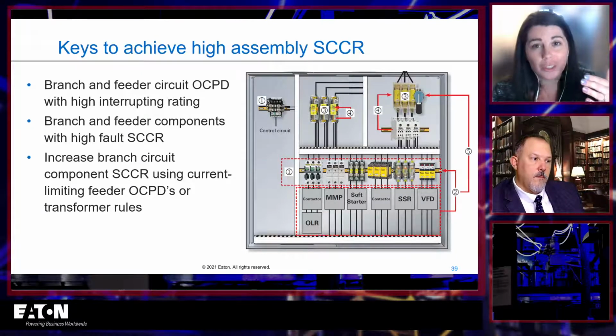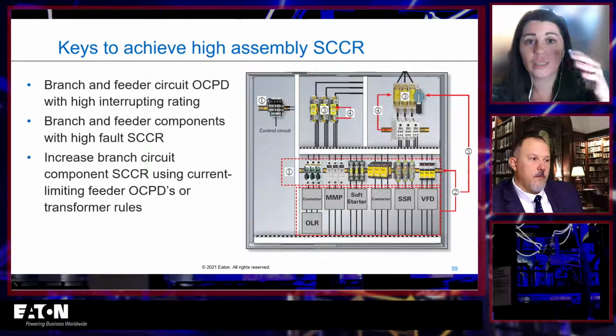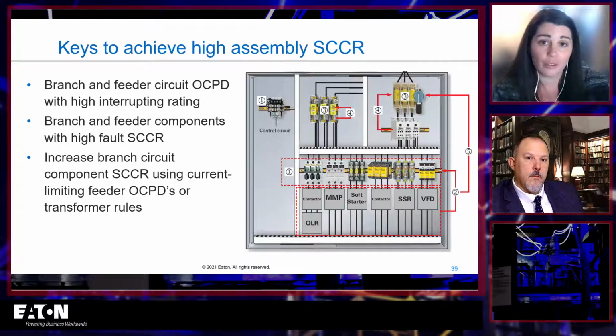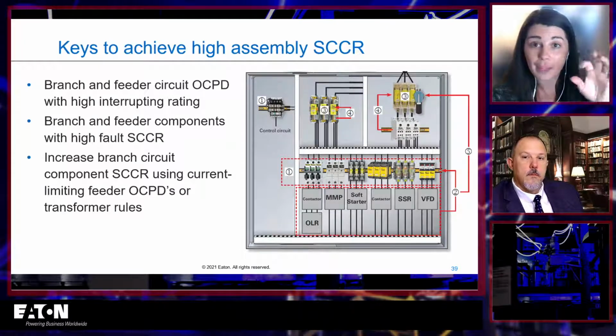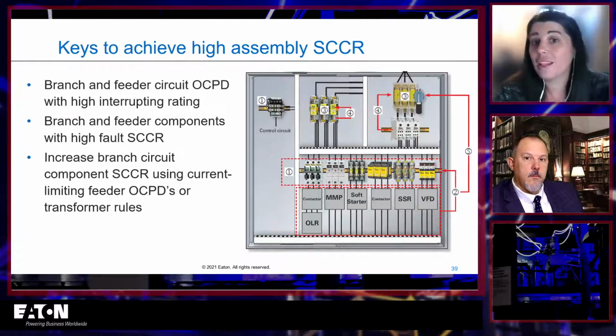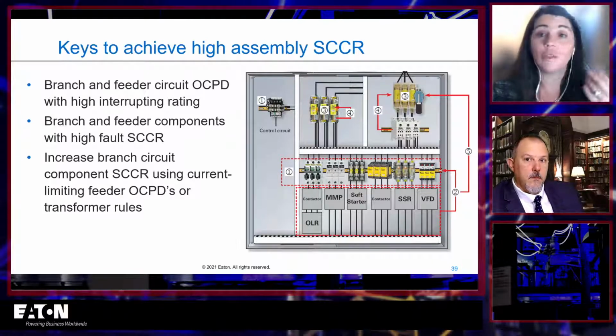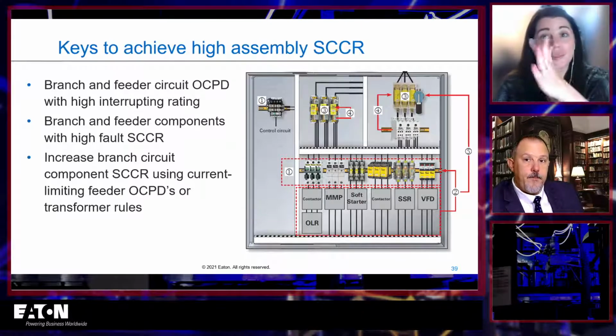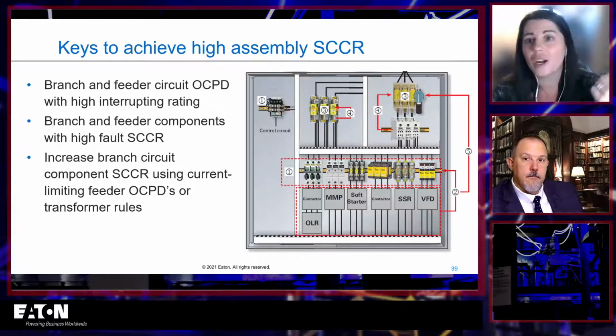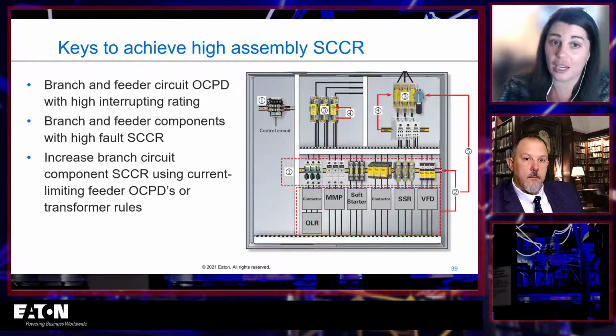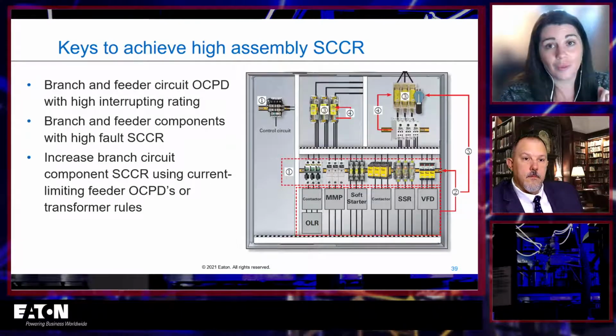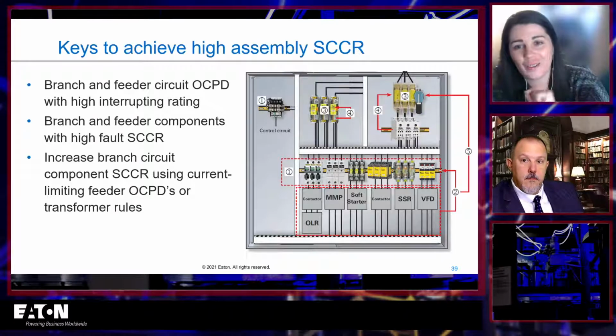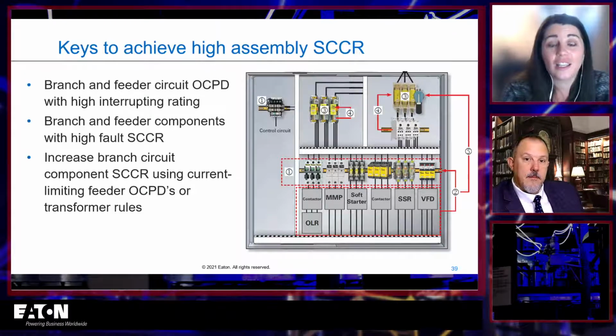Low short circuit current rating equipment usually comes from people who don't take advantage of that. They wind up with that standard, low fault rating because that component probably has a high fault rating if you use something specific in front of it, and they just didn't use that. They used something else which might cost the exact same amount of money, but you've got to use this one instead of this one, and now all of a sudden you have a high fault rating, based on what it's been tested with. So you want to use those combination or high fault ratings to increase your short circuit current rating, and then maybe use a current limiting feeder to help you. But that is very commonly misapplied, so don't apply that piece unless you sit through a whole training with me on what you can and can't do with that one. You can increase your rating with current limiting, but you have to follow a bunch of rules before you can do that.